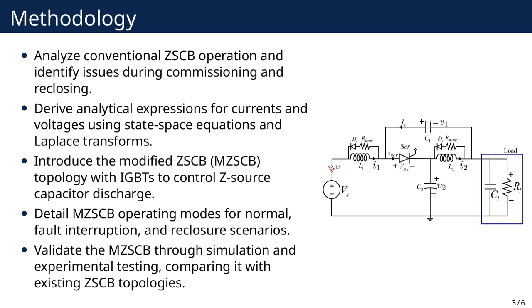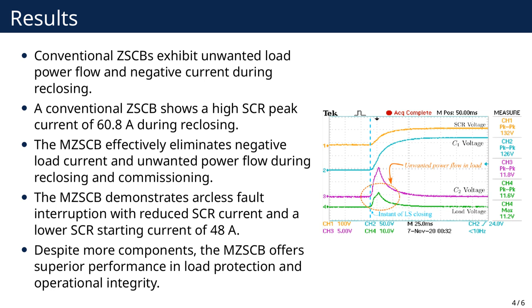The analysis of the conventional series Z-SCB revealed significant issues during commissioning and reclosing. Specifically, experimental and simulation results showed unwanted power flow in the load during commissioning, negative current flow through the load during reclosing, and a high peak current of 60.8 amperes in the SCR during reclosing. The proposed MZ-SCB topology effectively resolved these problems.